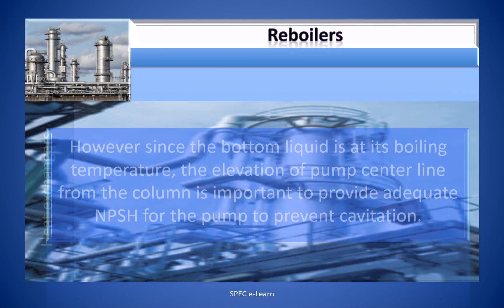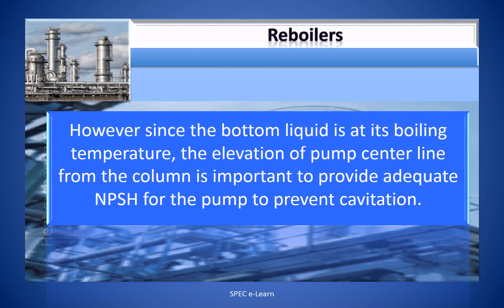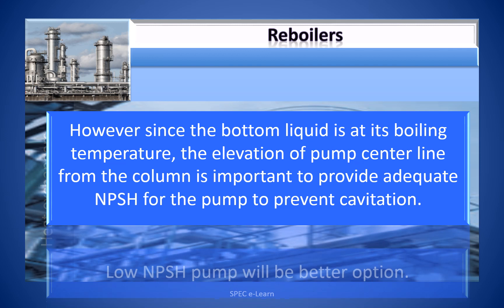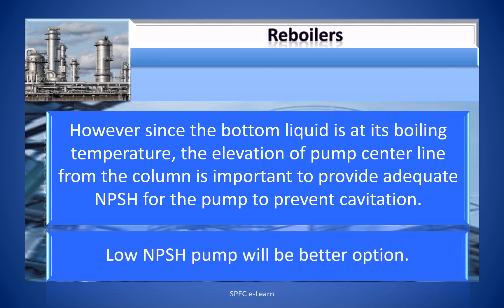However, the bottom liquid is at its boiling temperature. The elevation of the pump centerline from the bottom of the column is important to provide adequate NPSH for the pump to prevent cavitation. A low NPSH pump will be a better option.